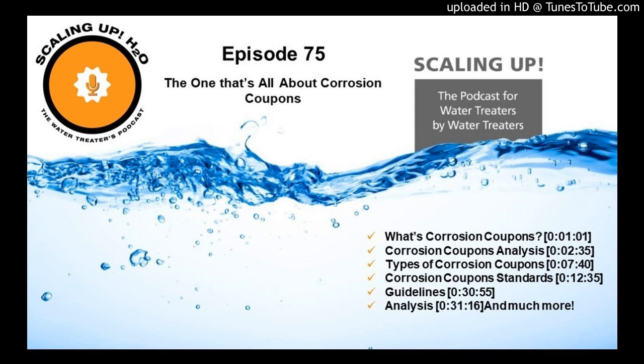I will urge each and every water treater out there that if you are not using corrosion coupons, to please consider to start using that, because again, the only way you are going to know that a problem is coming is once a problem is there. There's no proactivity if you're not periodically looking at what your corrosion rates are. Now, a lot of people ask me, do I prefer corrosion coupons or do I prefer the electronic corrosion coupon monitors? And of course, the more data sets that you get, the better it is. But those are expensive.